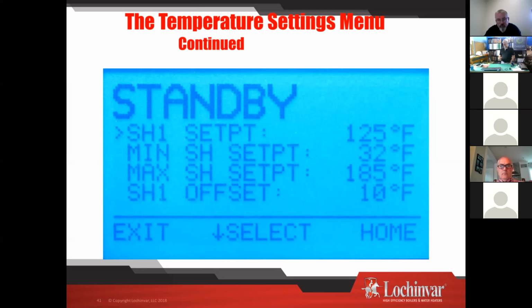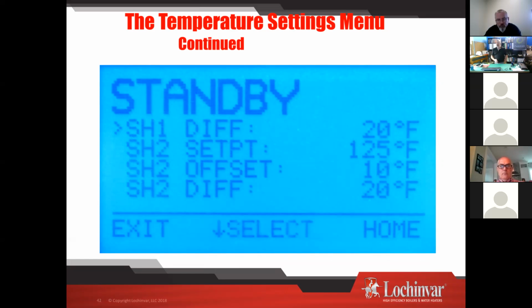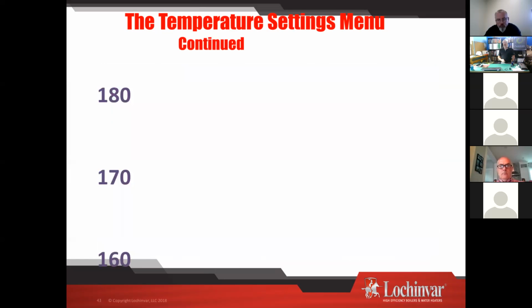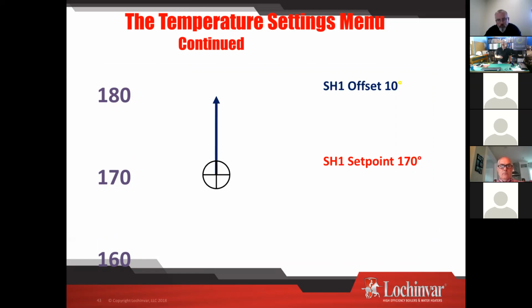Now offset, our offset works with our differential. And what it does is it works something like this. If I am targeting 170 degrees, that's based on my outdoor reset calculation, whatever it is, 170 degrees, I set my offset for 10, which is the default setting. Basically, when my boiler gets to 170, I'm going to idle. Now, if I reach that 10-degree offset of 180 degrees, I will shut off. And then my differential comes into play. And I will cool down to that 160. When I get to 160 or 20 degrees below my offset, I'm going to fire back on.